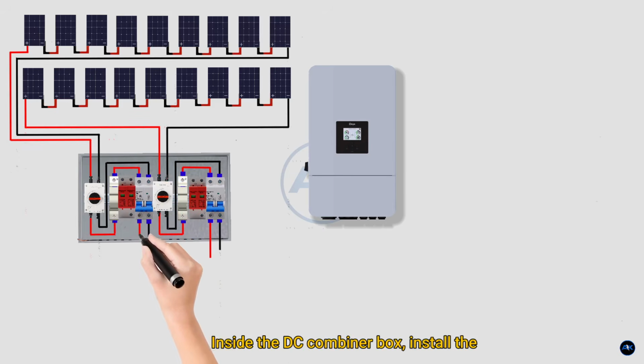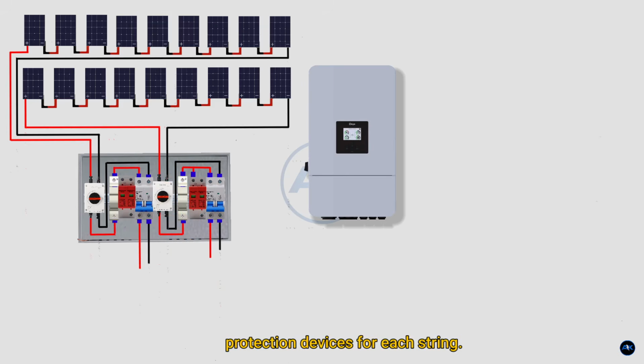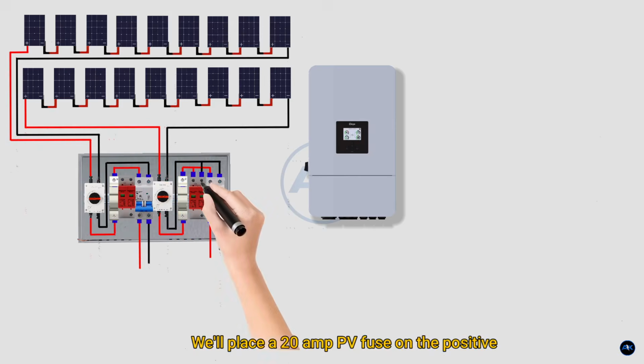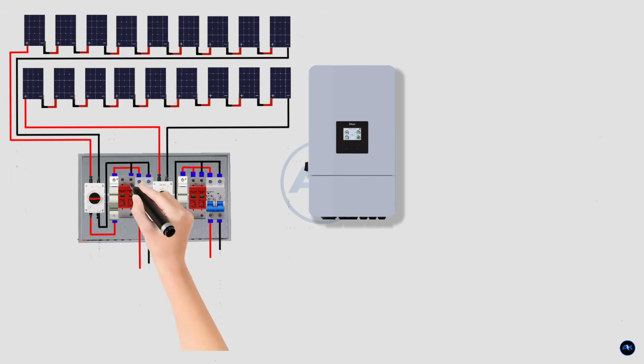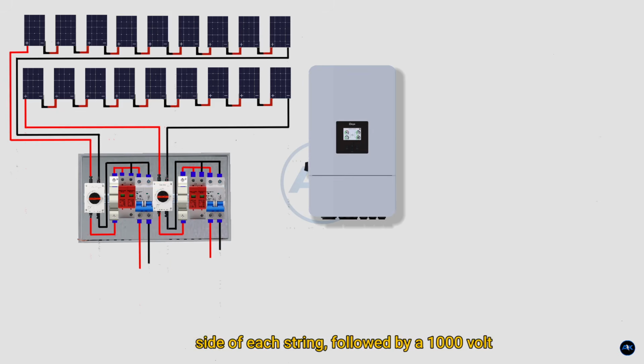Inside the DC combiner box, install the protection devices for each string. We'll place a 20-amp PV fuse on the positive side of each string, followed by a 1,000-volt DC surge protection device. The combined output then passes through a 32-amp DC breaker. Finally, before the cables reach the inverter, we install an external 1,000-volt DC isolator. This allows us to disconnect the solar array quickly for maintenance or emergencies.